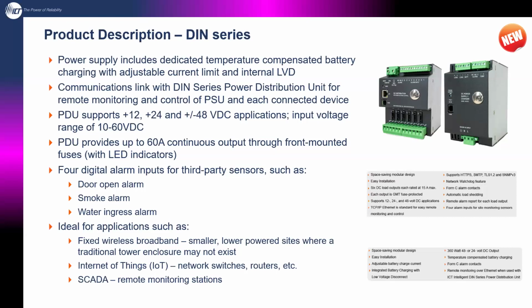This one has fuse protected outputs. It has an input voltage anywhere from 10 to 60 volts and can provide up to 60 amps of output power. We can connect temperature probes to manage and monitor ambient and battery temperature, ensuring we're charging your batteries at the best rate based on battery and outside temperature.